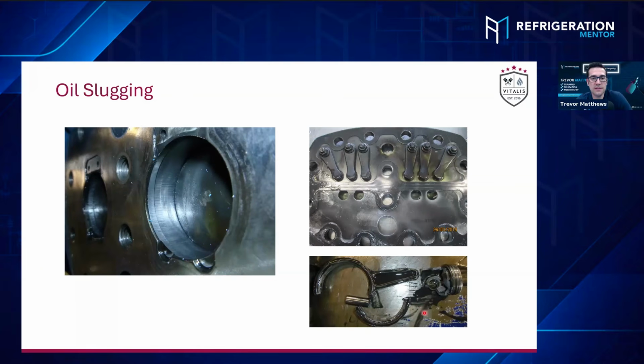Yeah, and one of the things is that this could happen from failed level control. All of a sudden, the solenoid turns on, and for some reason stays energized. The relay inside it fails, and it just stays open and just continues to feed oil and oil and oil into it, and then you just get too high of an oil level. One of the things is you just want to pay attention to this stuff. If you have a failed compressor, was it an oil slug or was it a liquid slug? By looking inside, it's going to tell you how much oil was even in there.